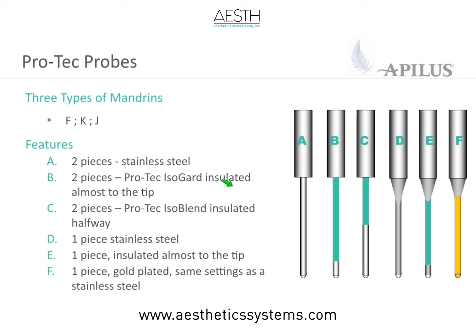When we go a little bit deeper, you can talk about insulated versus non-insulated. So what this diagram actually shows you is different types of insulated probes. The teal color here is signifying insulation. So this probe, for example, is a stainless steel, meaning there is no insulation at all. If you work with either one-piece or two-piece probes, but non-insulated, you would want to make sure that you keep the machine on the non-insulated settings. If you use the gold probes, that is another one where it is essentially a non-insulated probe. There's no insulation on the gold probe, it is simply gold-plated.